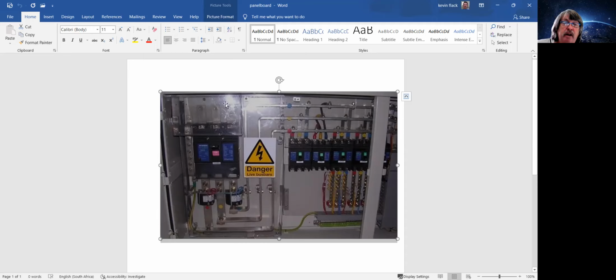This one here would destroy the main breaker, and if the energy shot through on this side, it might in fact start second and third level damage areas within the panel. Not something you want to do. The alternative is, of course, that everything has to be rated for that, rated from the kA level, which is very difficult if you've never tested your panel and you're just going to wire one to be effective from a load point of view.